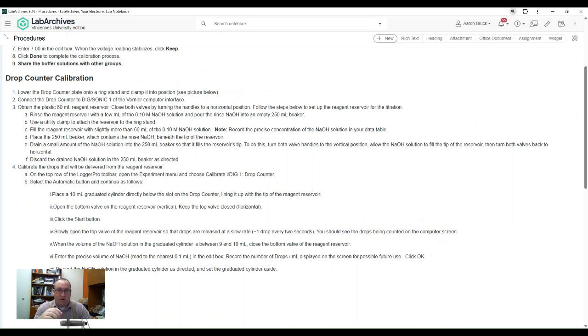You're going to measure the volume before you start the calibration. You're going to let it drop through, so the drop counter will count the number of drops over a given amount of time. You're going to measure the volume after at least a milliliter. The procedure says to start with a graduated cylinder that's lined up and set it up so that you're going to measure it somewhere between 9 and 10 milliliters. So you let it drop, let it do its thing, measure the actual value itself, and then it calculates the number of milliliters per drop based off of what you put in.